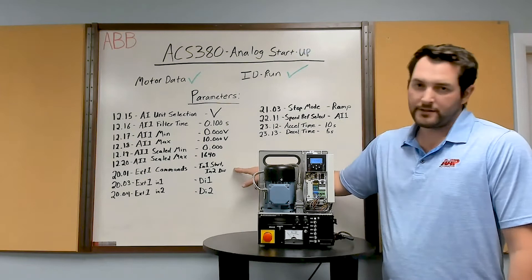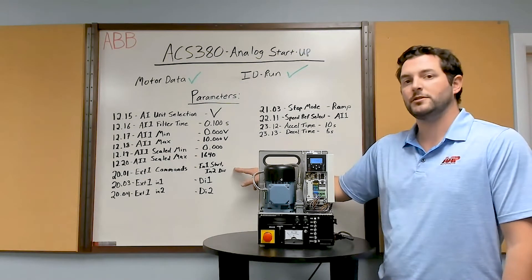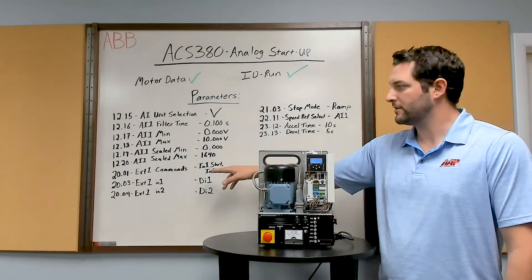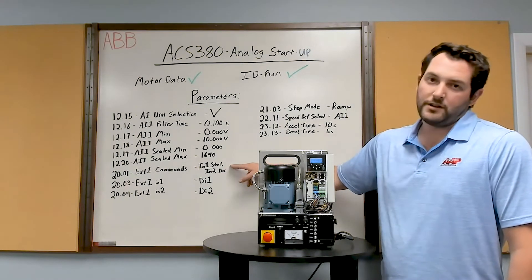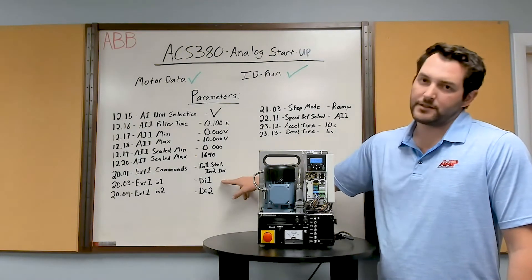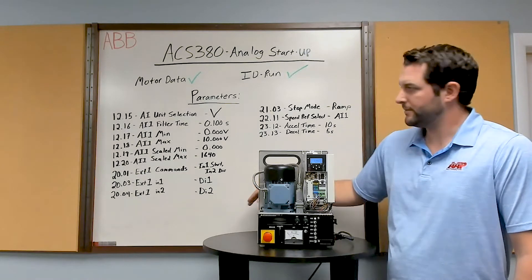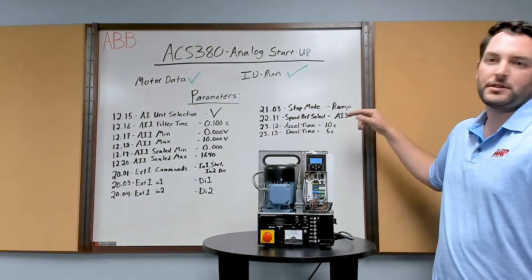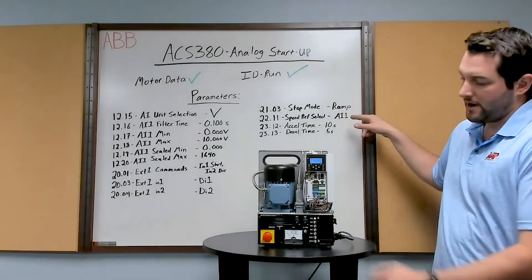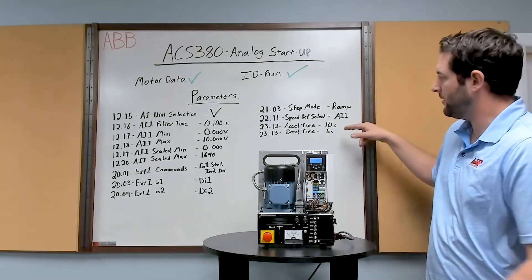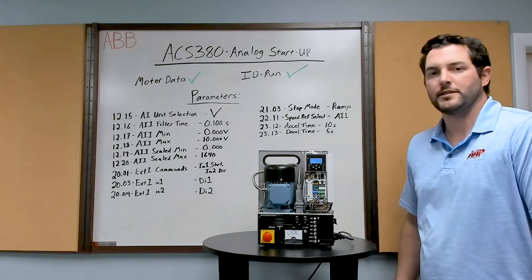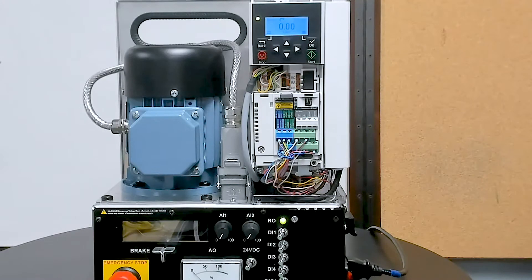Then we go down to our external commands — you can program multiple external commands, but since we're just doing a single analog input this time, we're only going to use the first one. We're going to use one to start and two to change the direction of the motor, and we assign those to digital input one and digital input two. Then we come over to our stop mode and we're just going to use the ramp — you can also use coast. Speed reference is analog input one. Our accel time is 10 seconds and our decel time is five; those can be adjusted to fit your application.